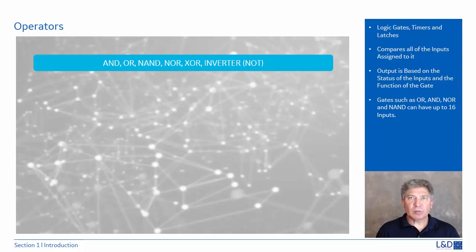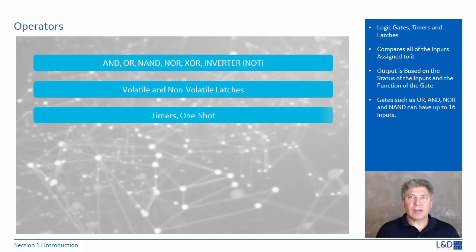The number of inputs are adjustable between 2 and 16 for the OR, AND, NOR, and NAND gates. Other operators consist of volatile and non-volatile latches, timers, and one-shots. The maximum number of one-shots in FlexLogic is 64, while the maximum number of timers is 32.